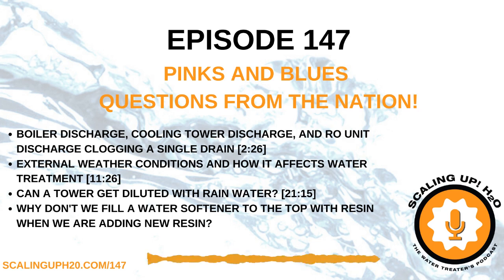Well, in that case, definitely it was raining all week, but rain didn't have anything to do with that tower having a low conductivity. It was the fact that it was overflowing. The tower level was set too high in the tower basin. I've also found where bleed valves have been leaking. Maybe the diaphragm was fouled up with some sort of debris. Maybe it was ripped. So make sure you understand what the true cause of an issue is before you write down what the reason for that issue is.